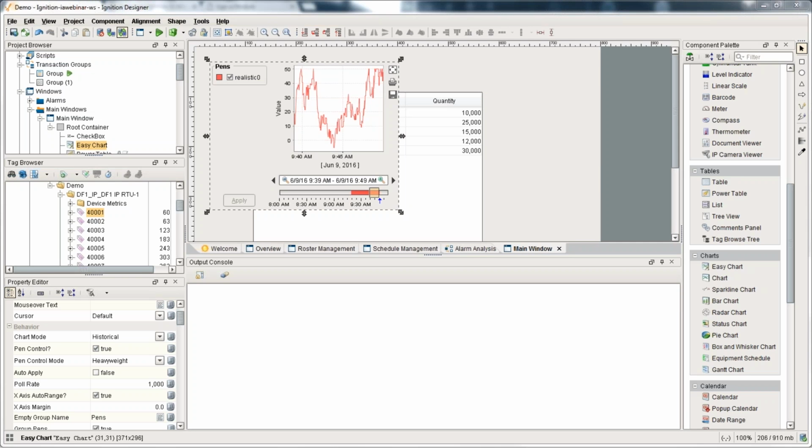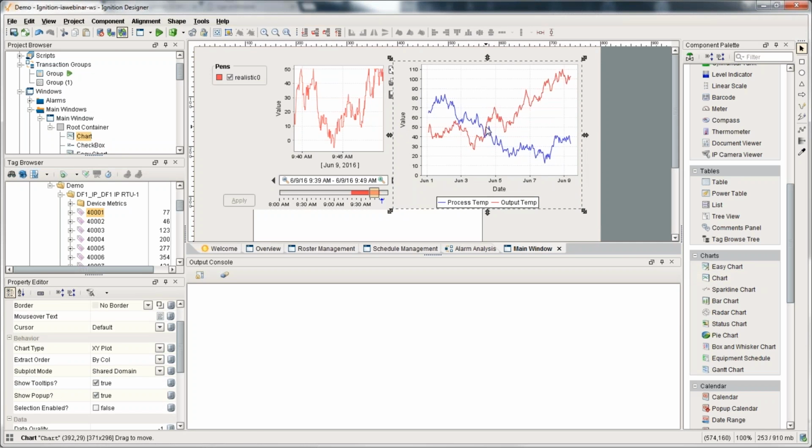Without the tag historian, it is possible to create a trend that is real time, where you can see the data come in, but when you close the window, it will get lost. It is possible to do that. Unfortunately, it'll be through scripting to actually add the data to that. There's an example in the forum on how to make a true real-time trend without any history modules for Ignition.